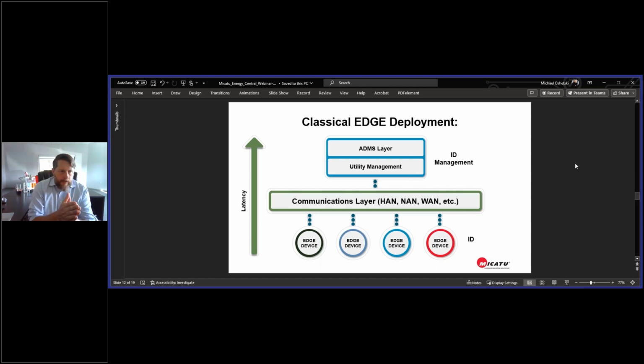Now, there are pre-programmed setpoints that we can do on edge grid devices. Yes, there are different devices we can pre-program, but I think it's a little bit more than that. The way we have to put this together isn't just having your control preset. For example, let's say you have a cap bank—it turns on at temperature X and off at temperature Y. Those are pre-programmed and pre-processed edge commands. But as we make digital twins and get this data, that can be modified—not only for your volt and energy consumption, but also based on predictive analysis of the weather to actually optimize your grid.